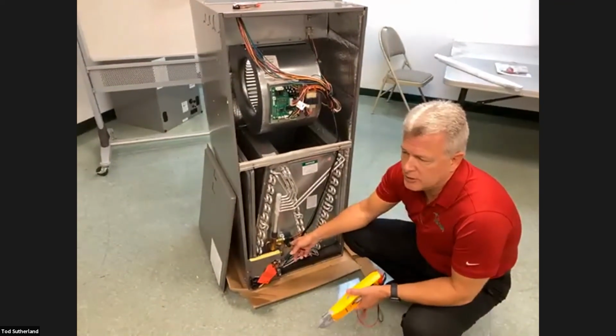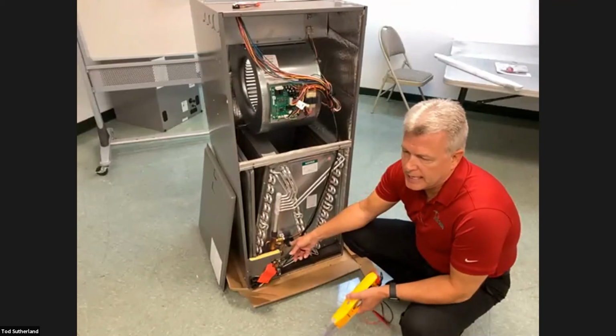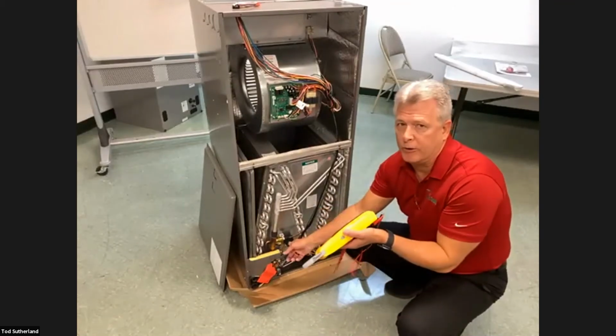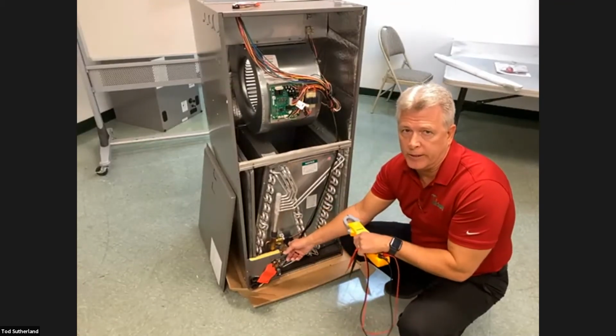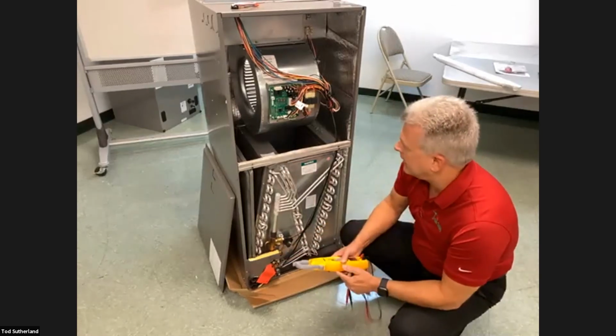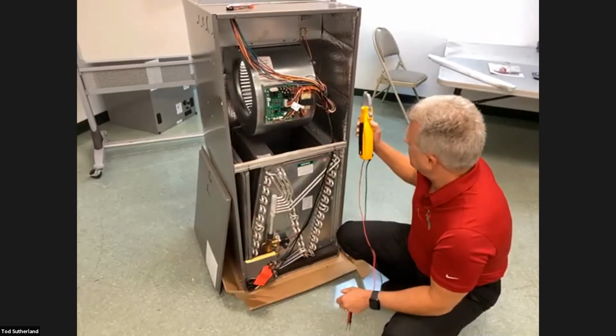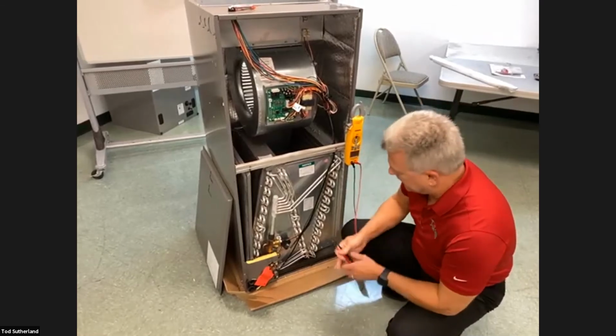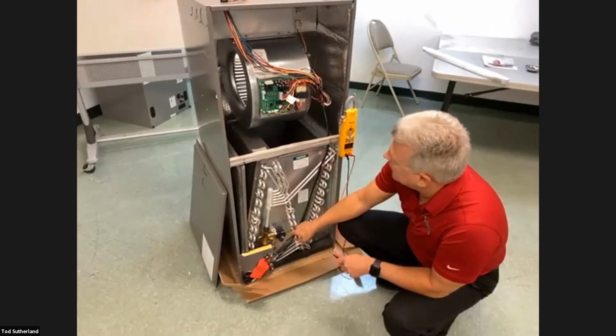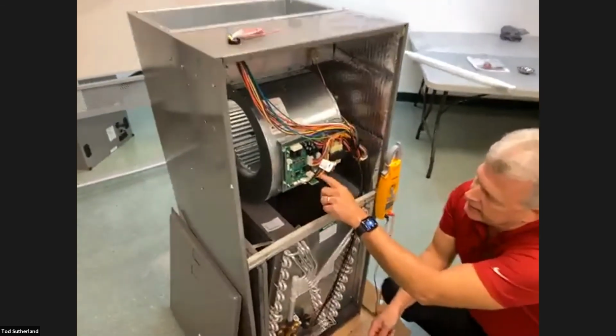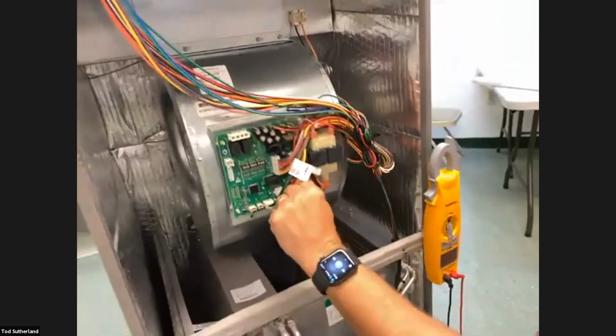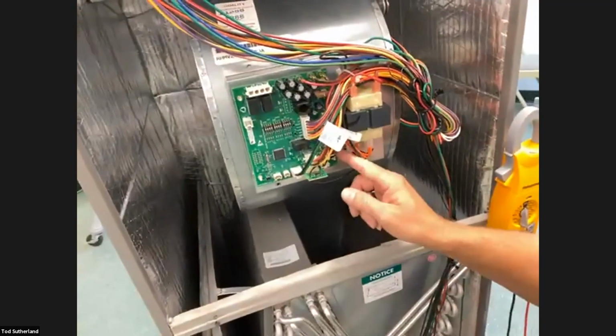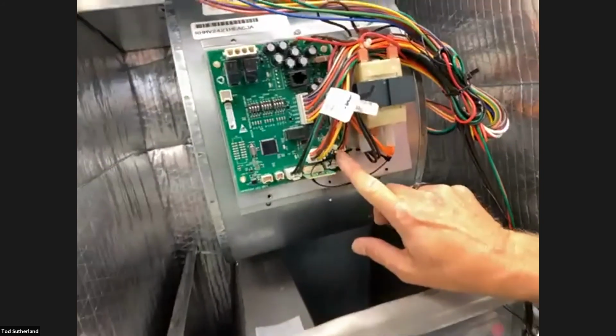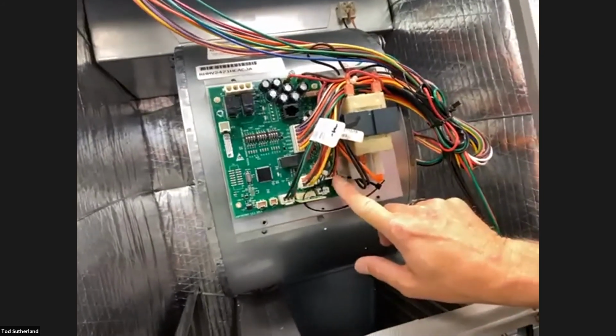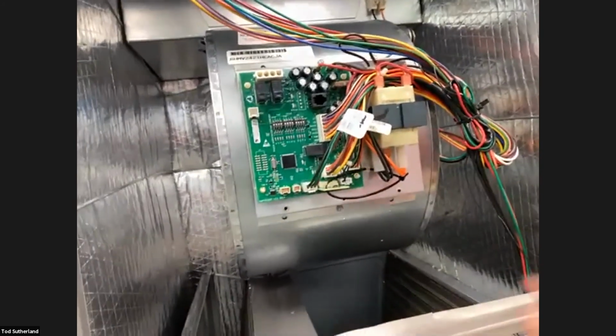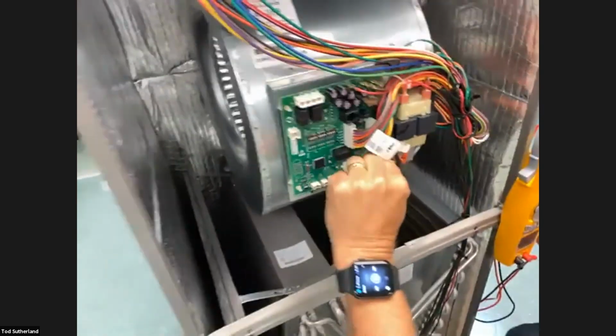So if you suspect that you have a bad stepper motor, you do have the option of pulling the one off of the outdoor unit and swapping it for the one on the indoor unit, okay? Can get you out of a bind on that. When you're checking the stepper motor, you're going to follow this plug back up to the board, and it's probably kind of hard to see, but you've got this plug right here that's gray, black, yellow, red, and orange. Okay, you're going to pull that off of there.